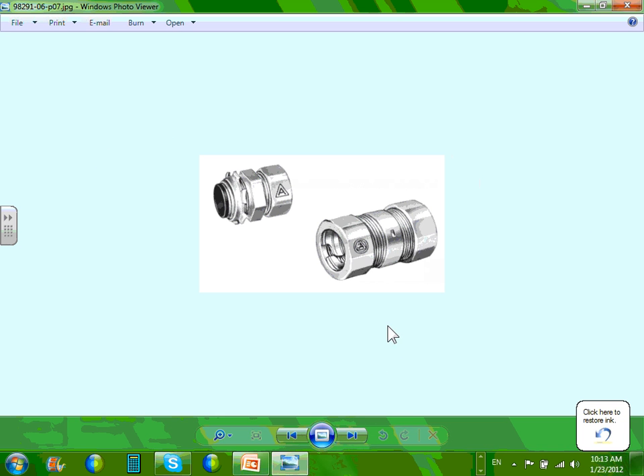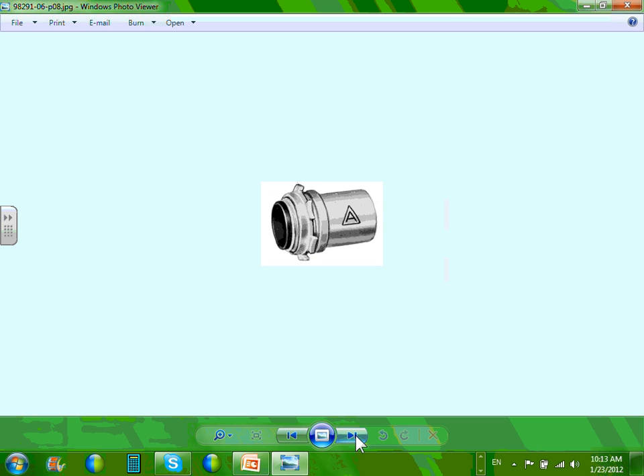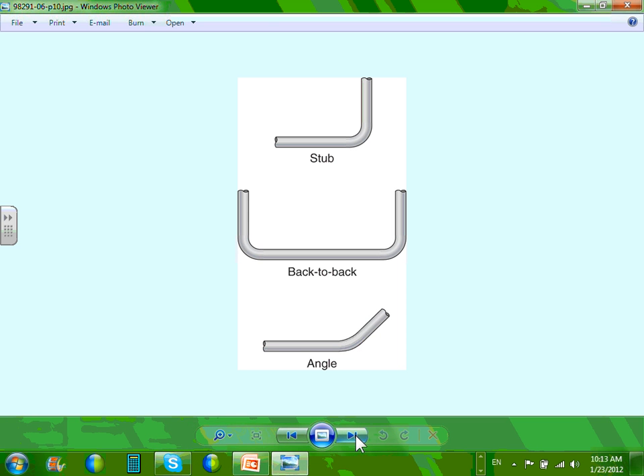especially that particular one, because these are compression connectors, guys. If you're outdoors and using EMT above ground, these are the connectors you're going to be connecting with. Compression connectors. These are watertight. So if you're using EMT outdoors, make sure you use this type of connector. Again, you guys are not electricians, but be aware of that one outdoors in a wet location. Different types of connectors for different applications.